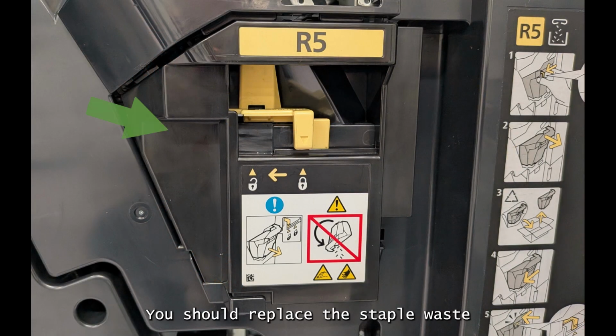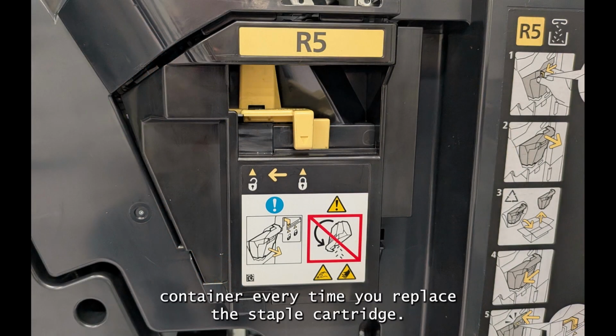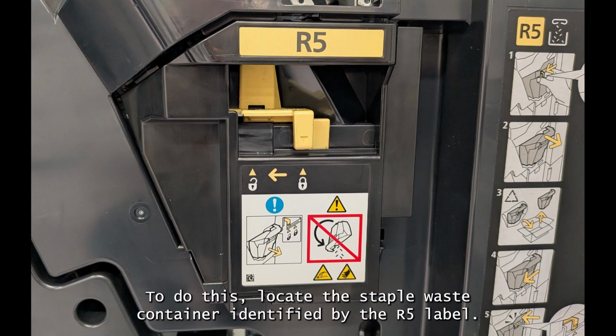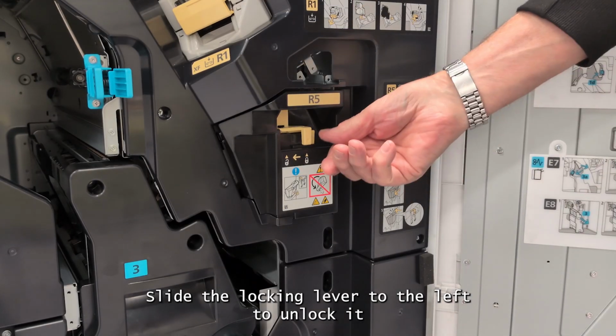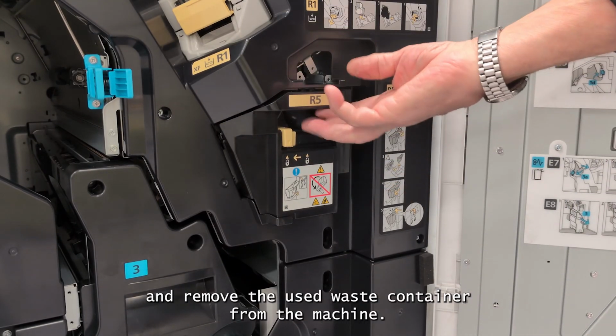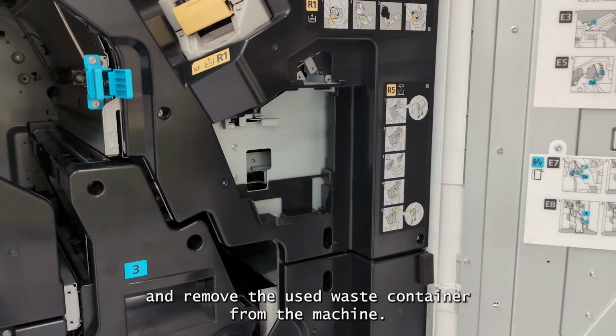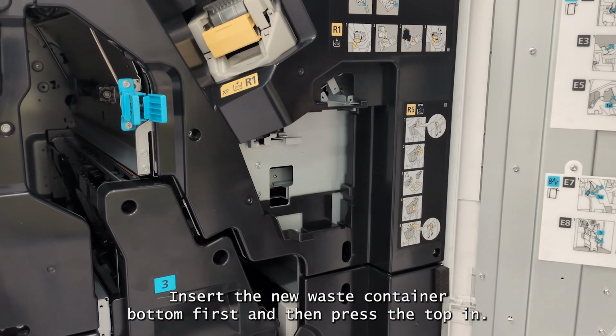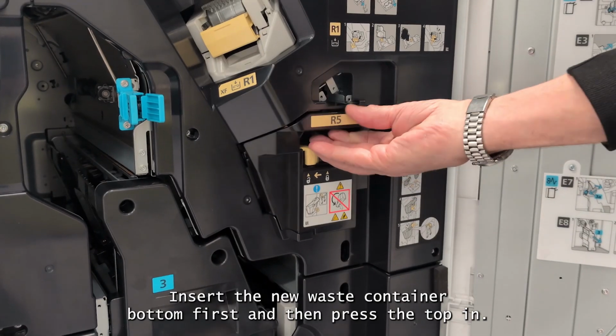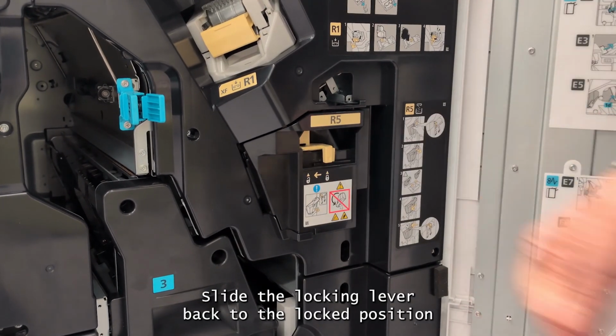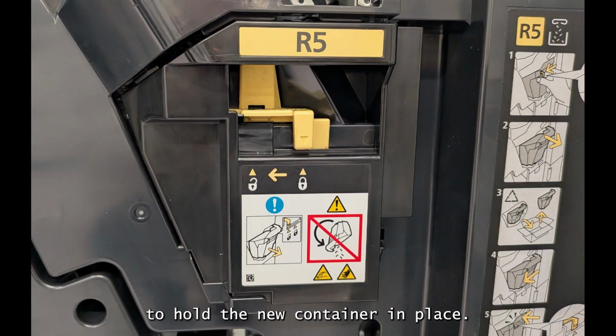You should replace the staple waste container every time you replace the staple cartridge. To do this, locate the staple waste container identified by the R5 label. Slide the locking lever to the left to unlock it and remove the used waste container from the machine. Insert the new waste container bottom first and then press the top in. Slide the locking lever back to the locked position to hold the new container in place.